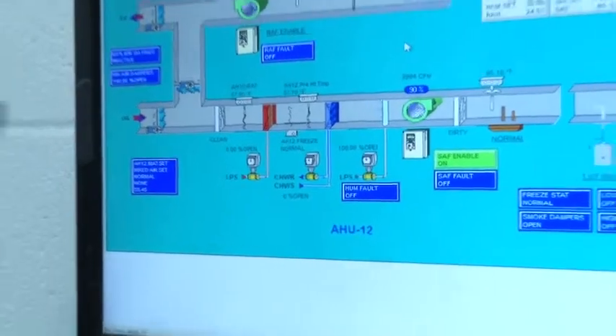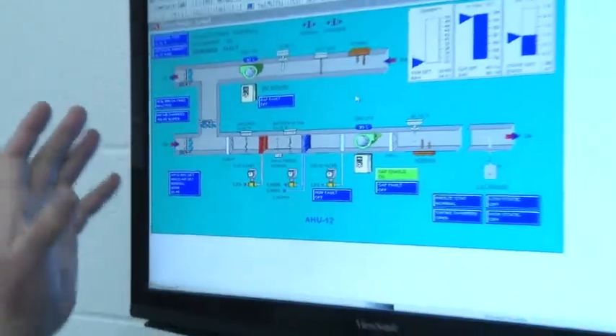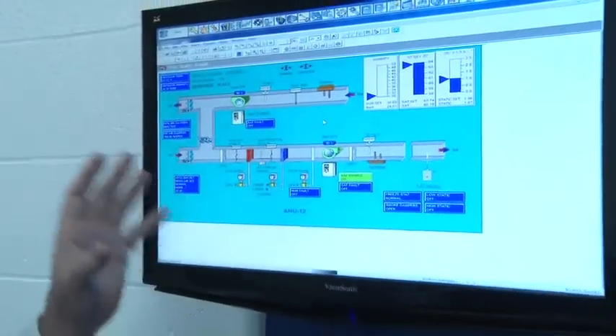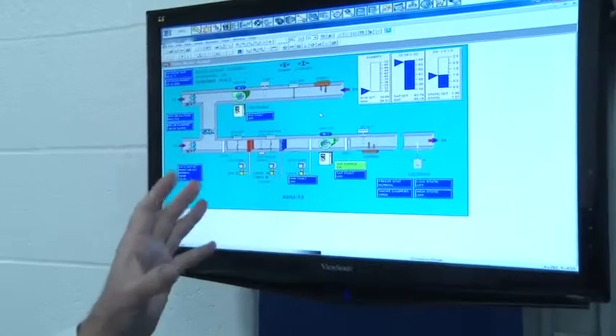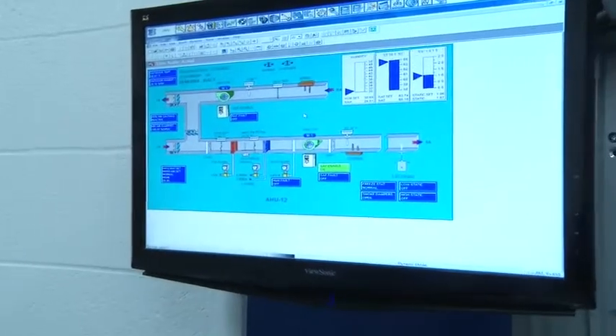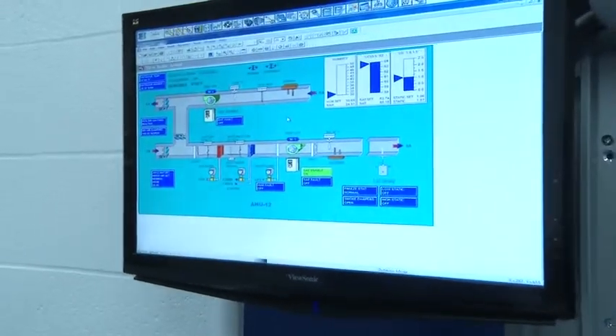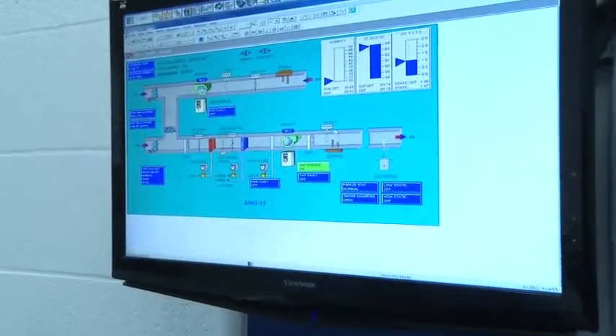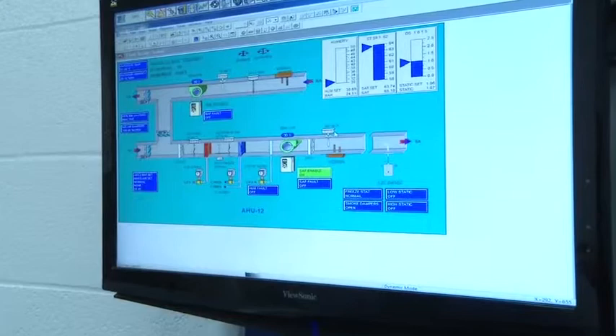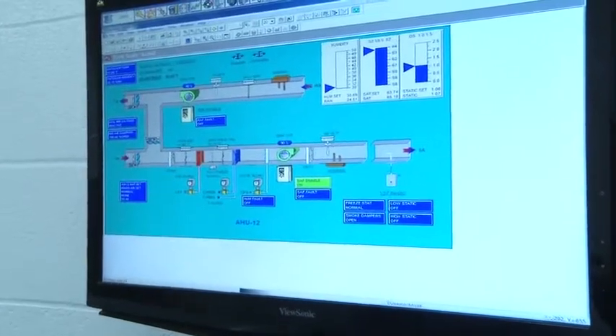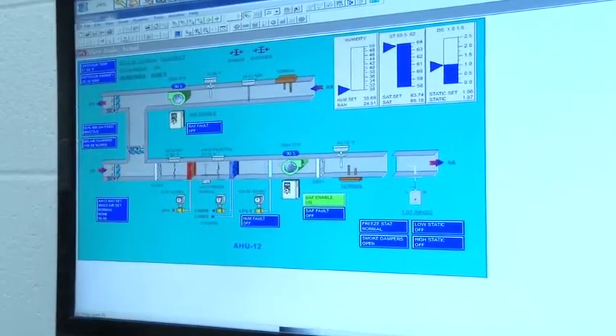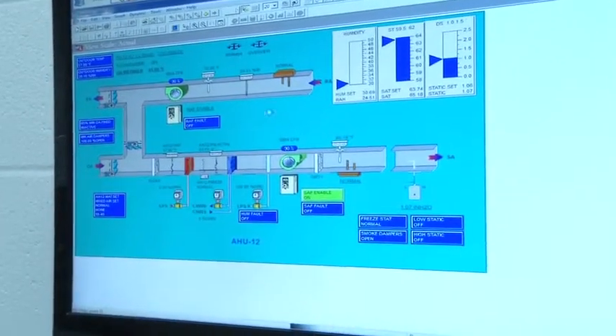This particular air handler has to run on 100% outside air, or 65% outside air. So we have to have special controls so that when the humidifier kicks on and brings in a bunch of extra heat, we can modulate our outside air dampers.